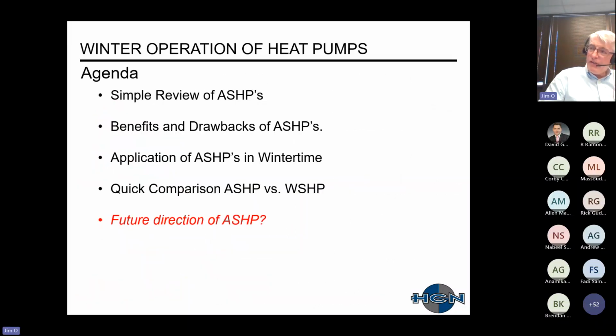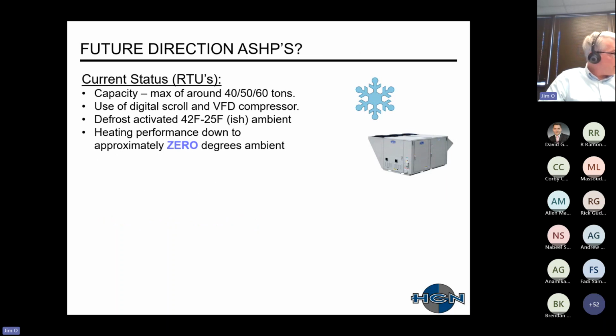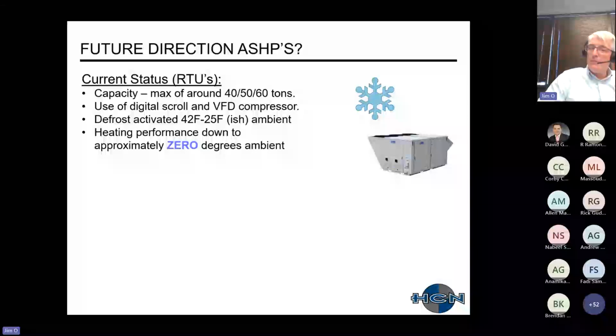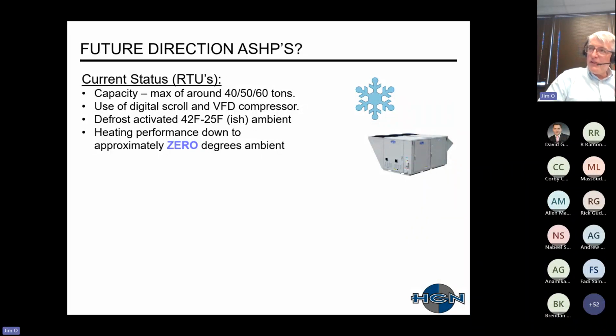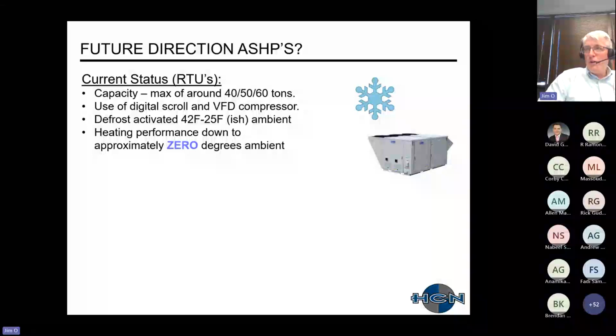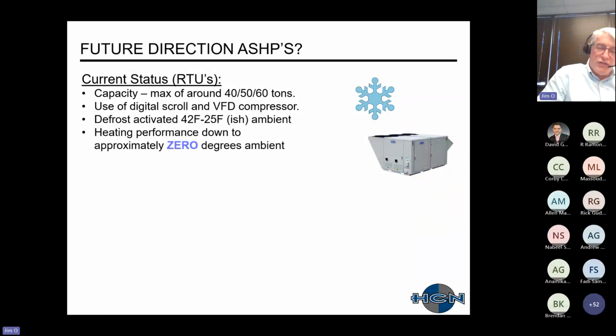And then, coming to the end here, just a future direction of air source heat pumps. This is my old-fashioned, old fogey take on things. Just current status, once again, looking at rooftop units. These could probably also be applied to split systems. Right now, the capacity of the air source heat pumps is around the range of 40, 50, 60 tons. This probably changes per manufacturer. We'll also say this is what I'll call traditional pre-engineered units. An example would be AAON, Carrier, et cetera.